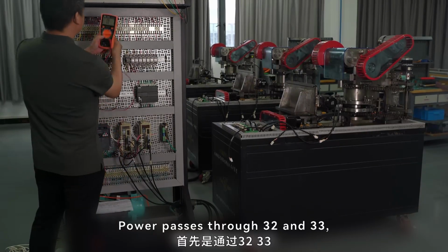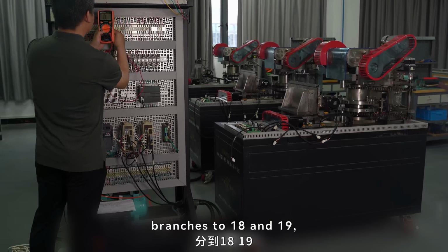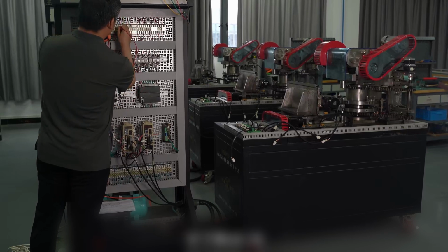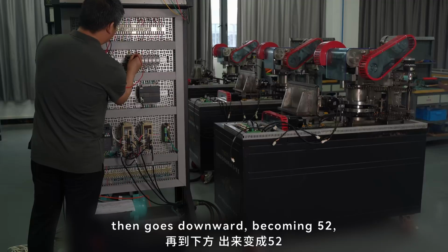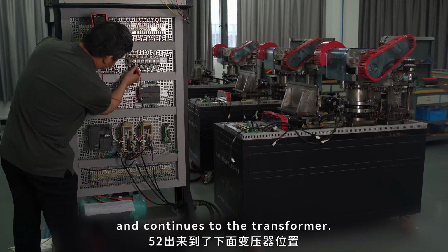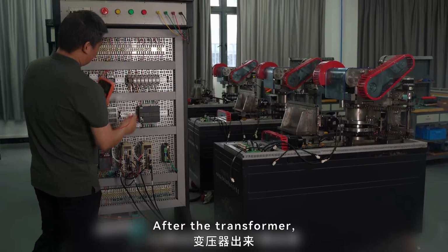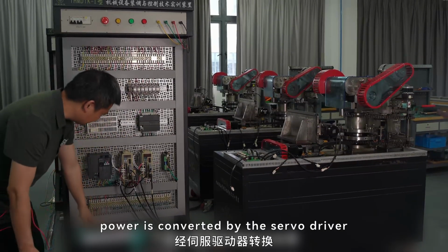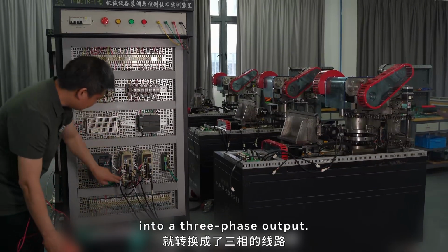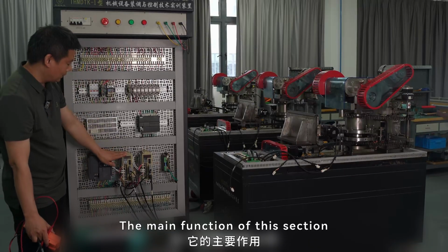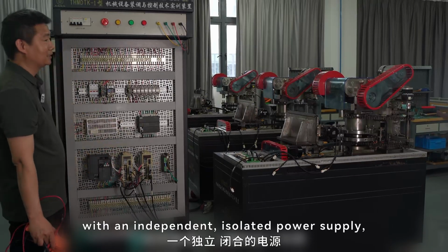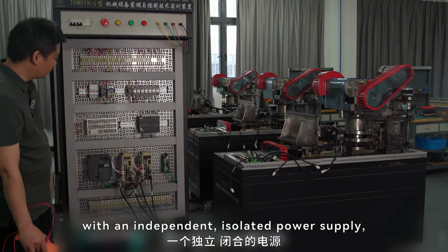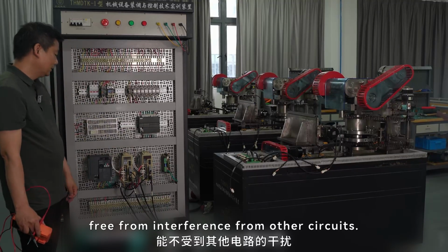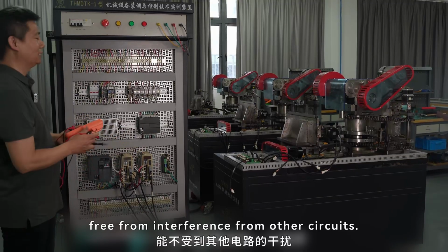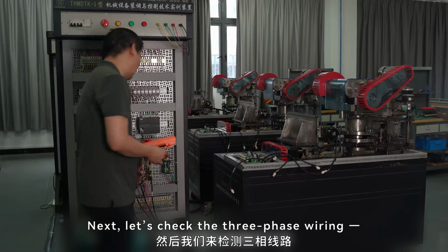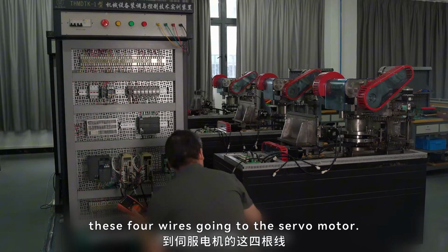Power passes through 32 and 33, branches to 18 and 19, then goes downward, becoming 52, and continues to the transformer. After the transformer, power is converted by the servo driver into a 3-phase output. The main function of this section is to provide the servo driver with an independent, isolated power supply, free from interference from other circuits. Next, let's check the 3-phase wiring, these 4 wires going to the servo motor.